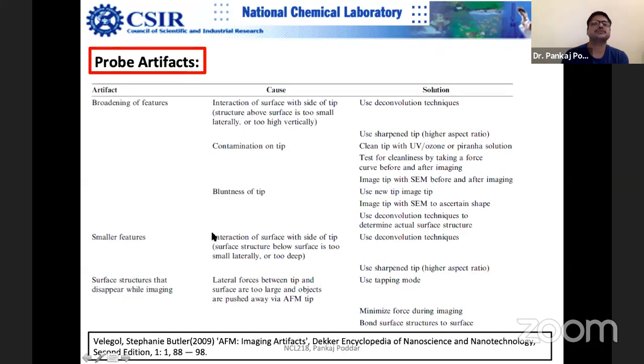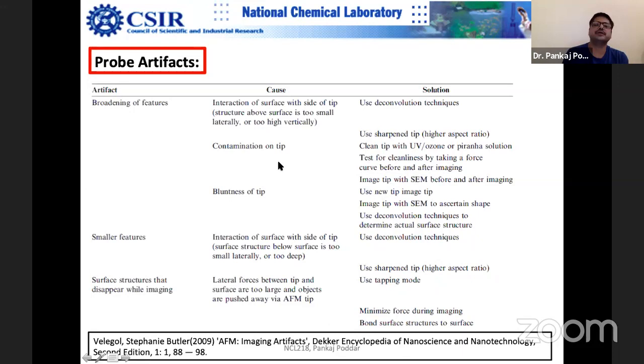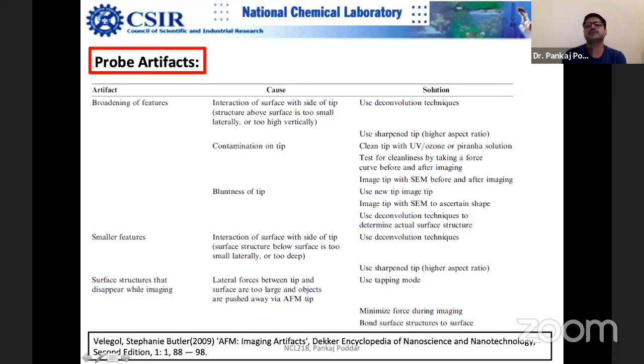One artifact is broadening of features. You may expect DNA width to be around 2 nanometers, or a particle size of around 10 nanometers, but instead get 20 or 30 nanometers. The causes are contamination of the tip, bluntness, sidewall interaction, and damage of the tip. Solutions include offline deconvolution, using sharpened tips, and cleaning the tip using UV ozonizer. At NCL we have a UV ozonizer that can burn off organic contamination using ozonization. You can also use piranha solution.